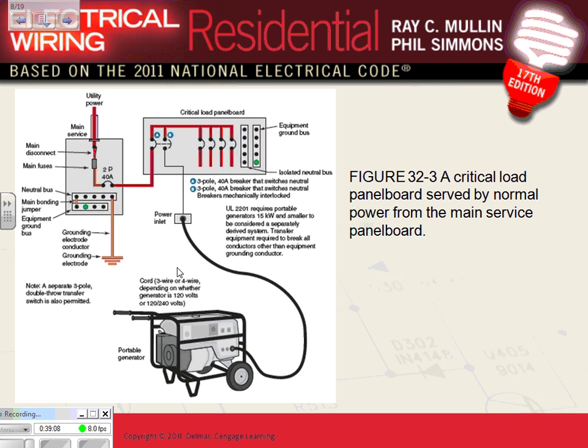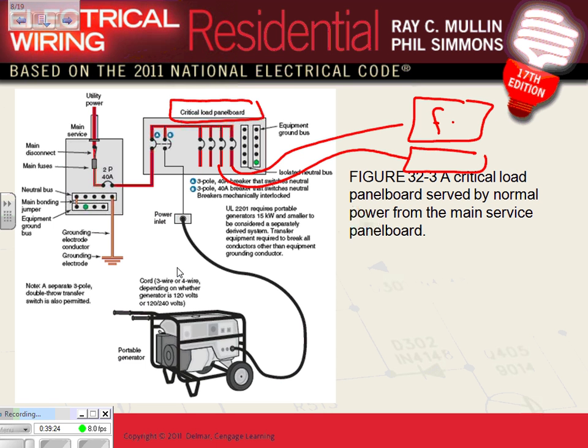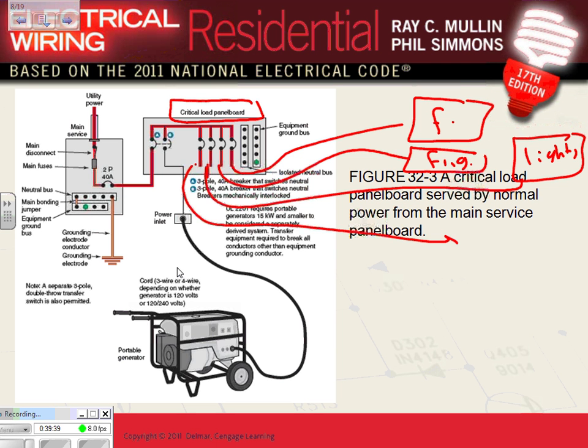And that outlet will feed a critical panel that could be in your garage. The critical panel right in here could be in your garage. This panel will feed certain loads from in here. One major load is the furnace. Another load that I could be feeding is my fridge. I don't want my food to go down. A couple of other loads that I can feed here are certain lights. What else can I do from there? Here's another load that I can do here. Fridge, furnace, what else? Sump pump, if you have a sump pump. I want my sump pump to be backed up.